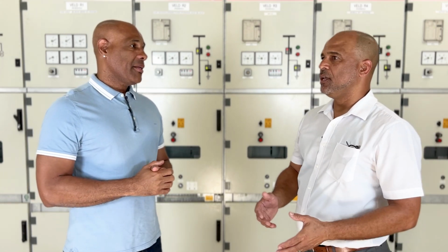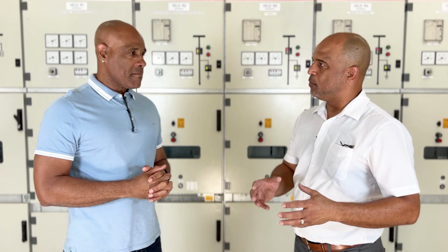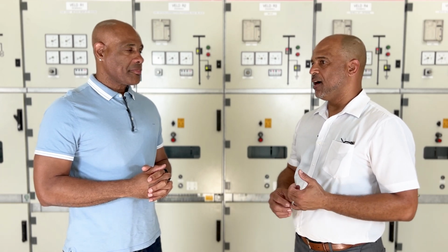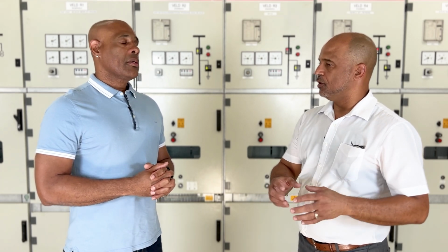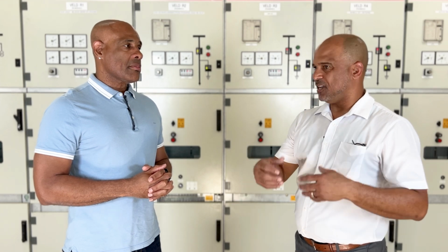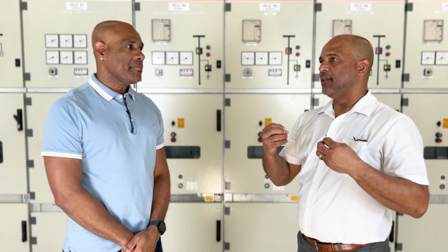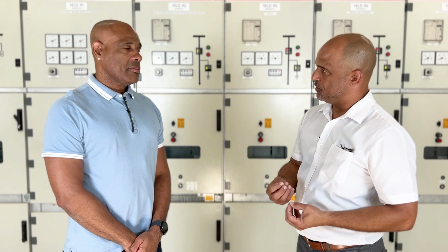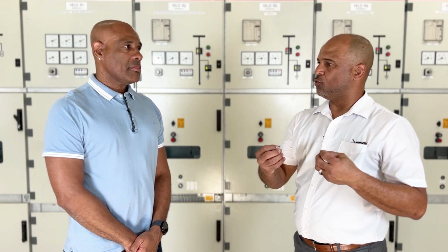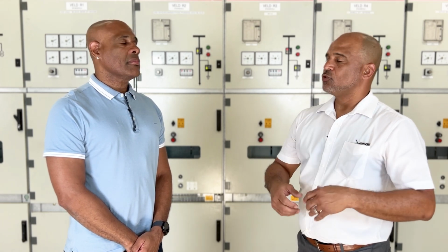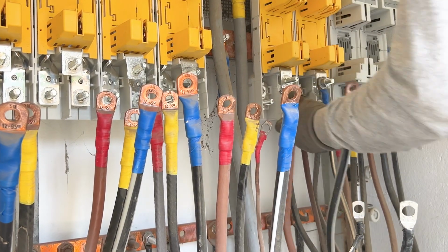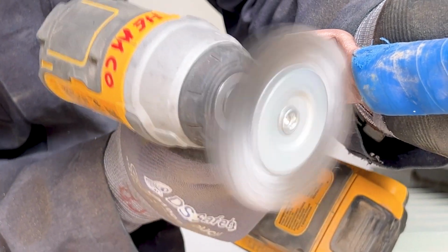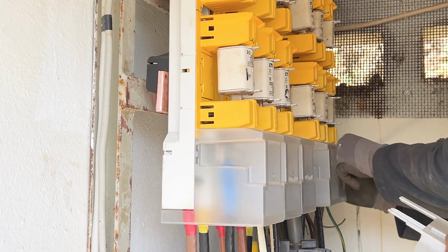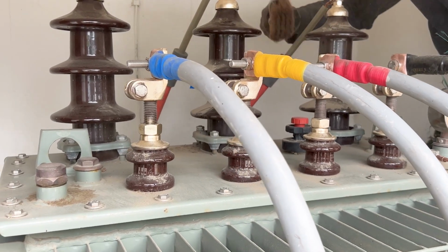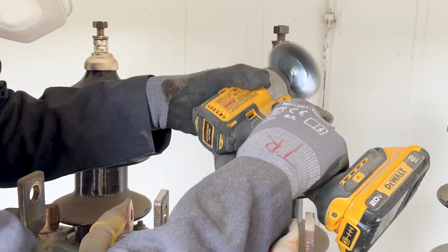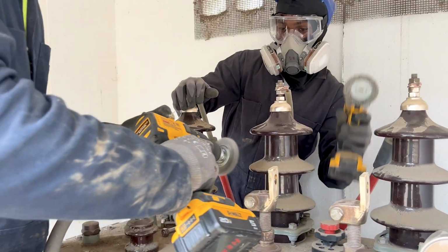So basically every, say, 5 years, we do maintenance on a transformer, because sometimes you get corrosion buildup on what we call the low voltage bus bars. They are exposed, they are open. Okay. So our environment is aggressive. So what happens is you get corrosion on the copper bars. So what we do is disconnect all the cables off the copper bars, polish the copper bars, and then reconnect all the cables back on. And also we do that with the transformer. So we take the transformer, clean it completely down, polish all the cable shoes and put them back.